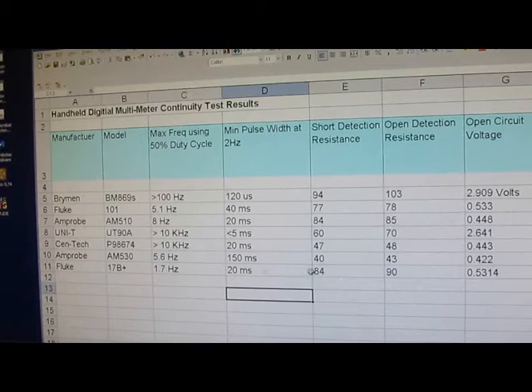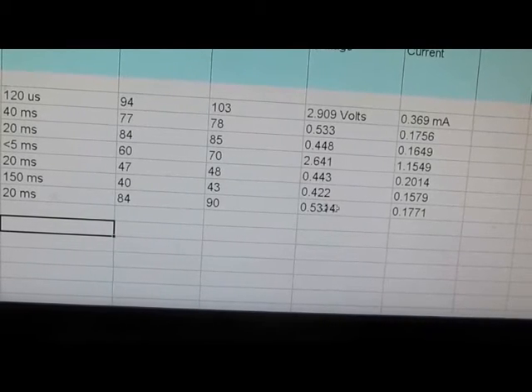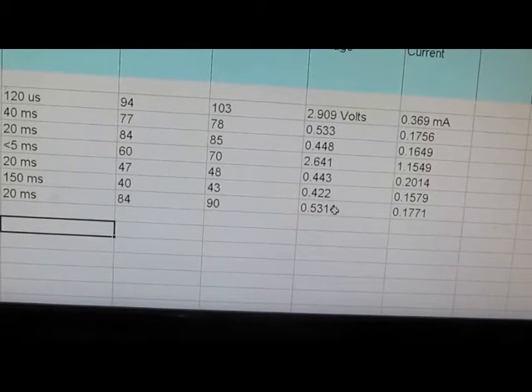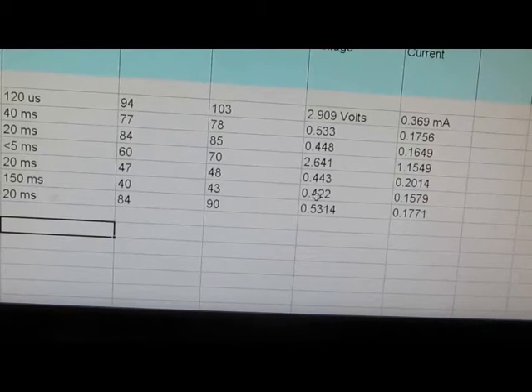You can see the Fluke is at 84 ohms where it detects the short, versus the Amprobe 530 at 40 ohms, and it releases at 90 ohms, so giving you roughly a 6 ohm hysteresis compared to 43 ohms or a 3 ohm hysteresis on the Amprobe 530. You can see the open circuit voltage for the Fluke, it's in the ballpark. It's 0.531 versus 0.422 for the Amprobe. Current wise, it's 177 microamps for the Fluke, 158 microamps for the Amprobe.